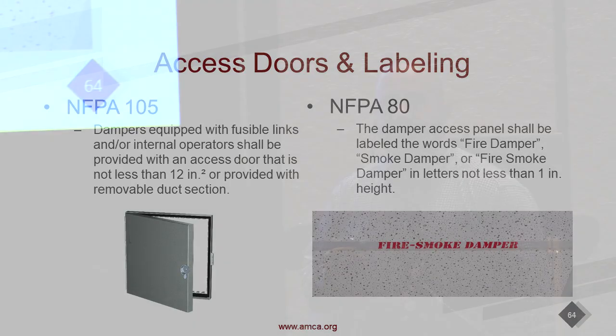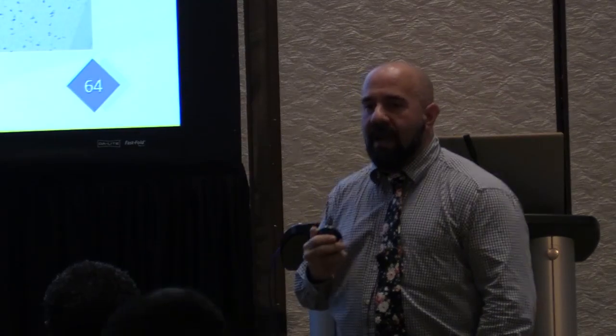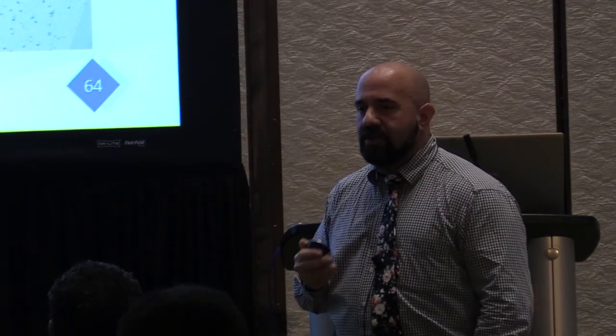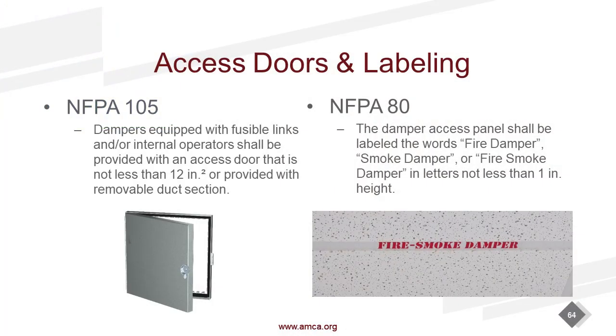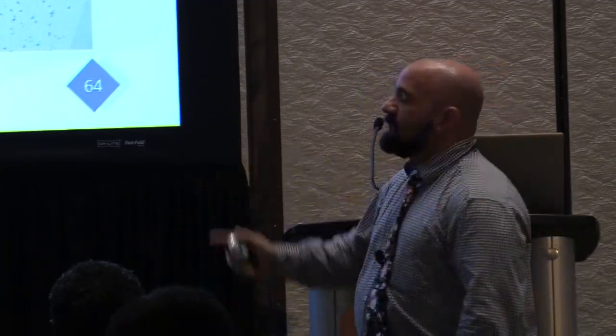So our 6x6 dampers require an access door of 12 inches square or a removable duct section. Remember that. And of course, we should be labeling dampers outside the access panel. I play this game. I go to the hospital a lot, unfortunately, and I play this game all the time. Find the damper. You've got a couple hours to kill, just walk around looking at the ceiling for those signs. You don't see them in many other occupancies but hospitals, but they are there.